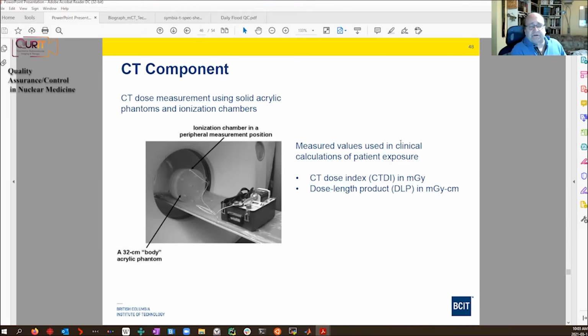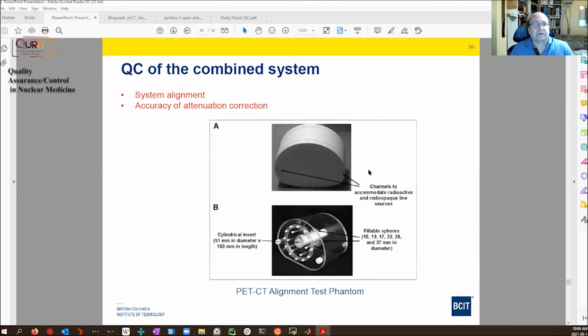There's actually various versions of that. And then for the settings, we can come up with another number for a certain scan of a certain length through the patient. We come up with the dose length product. So these numbers appear when we do a CT scan, and they're based on these measurements. And so we can assess what the patient dose is.